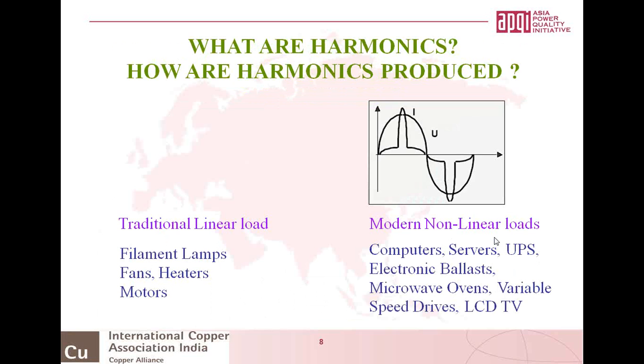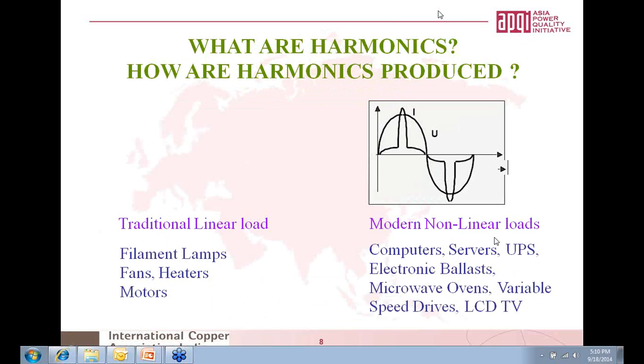And all of this reduces the service life of equipment, which requires early replacement. In fact, it has been seen that the reduction in life is estimated to be about 32% for single-phase machines, about 11% for three-phase machines, and 10% for transformers, only due to harmonic effects. So if these harmonics can be minimized, and if remedial measures can be taken, either retrofitted or initially during the design, we stand to save a lot of great losses.